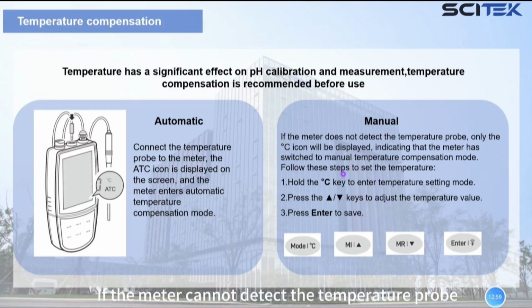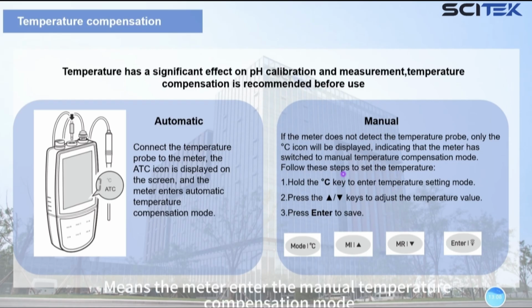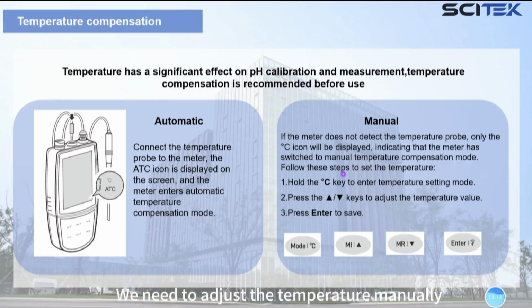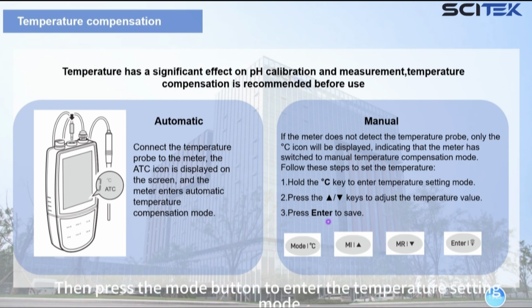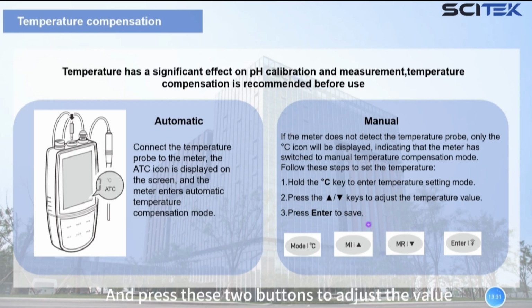If the meter cannot detect the temperature probe, only the degrees Celsius icon is displayed, which means the meter entered the manual temperature compensation mode. We need to adjust the temperature manually. You need a thermometer, and put the thermometer into the buffer solution. Then press the mode button to enter the temperature setting mode and press these two buttons to adjust the value. You need to input the reading of the thermometer. Finally, press the enter button to confirm.